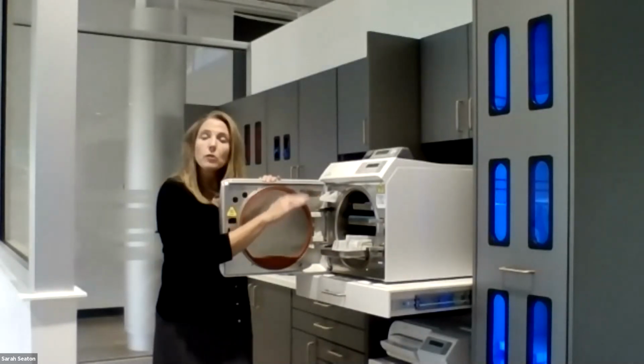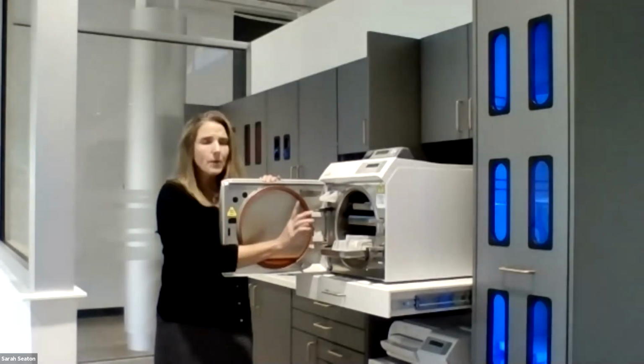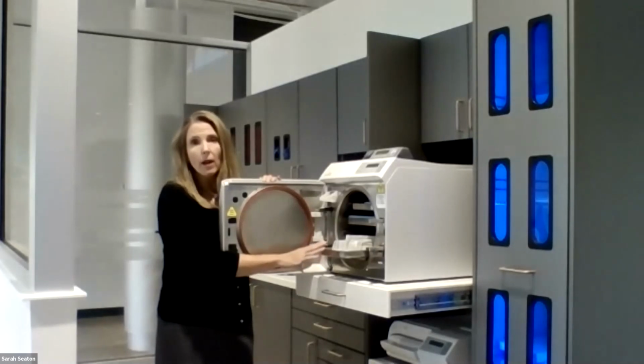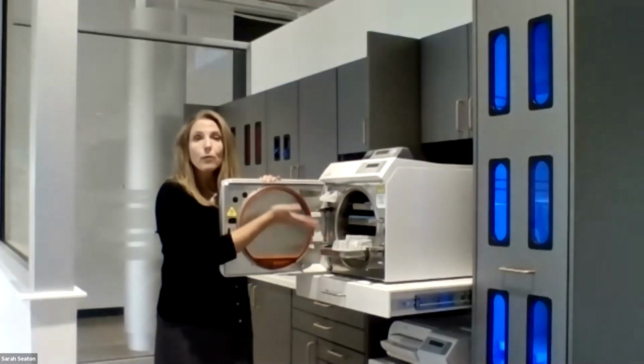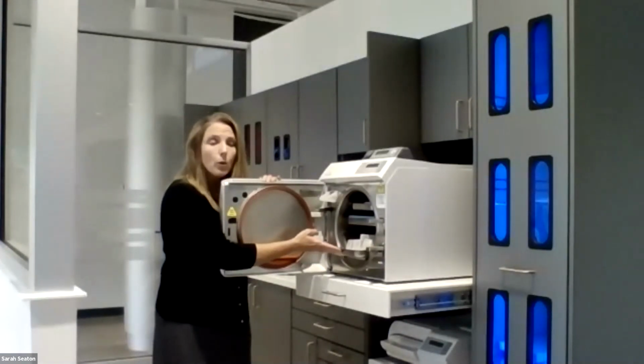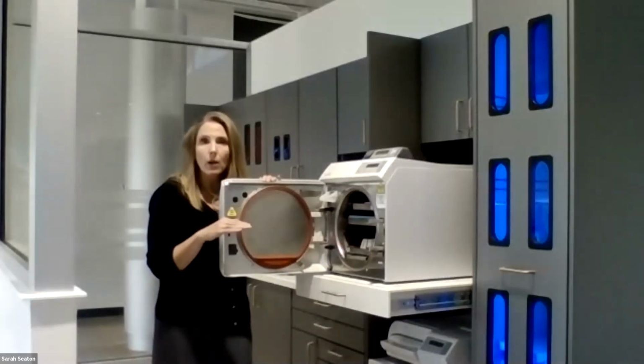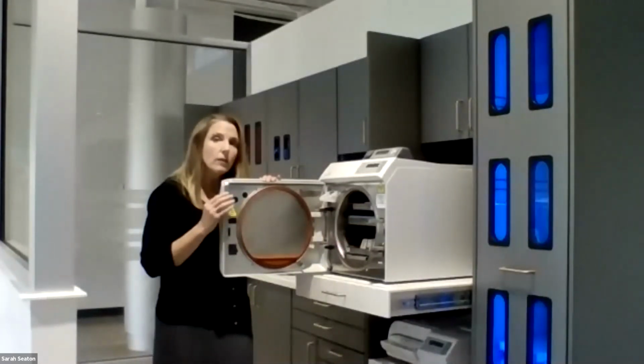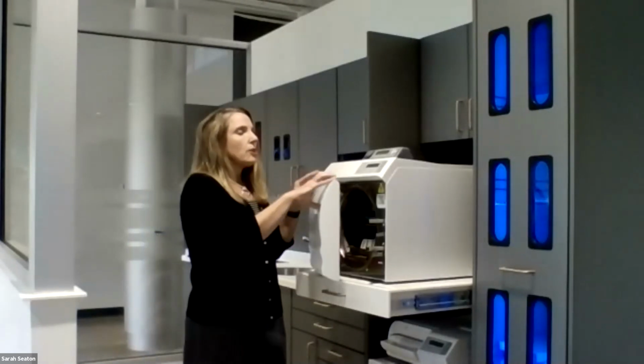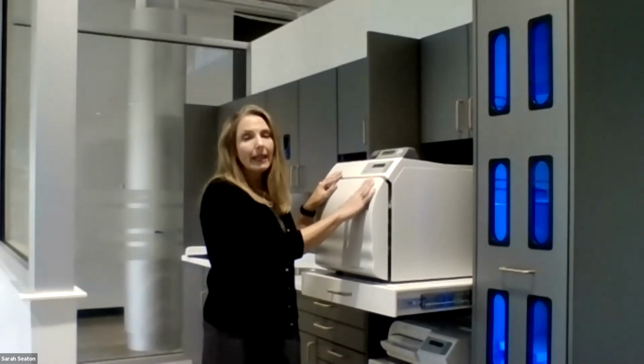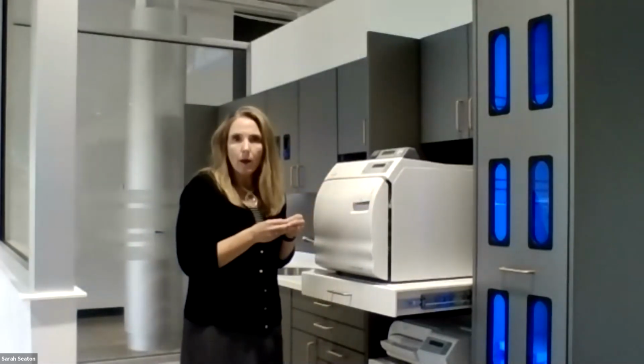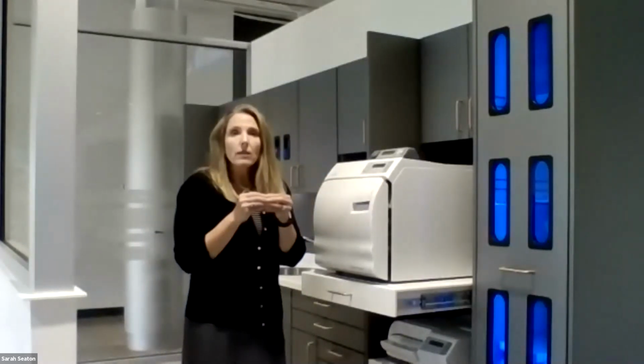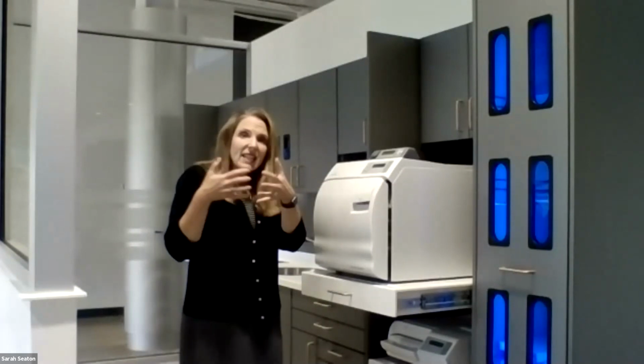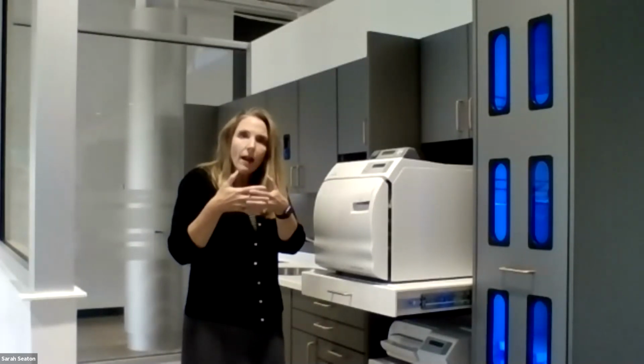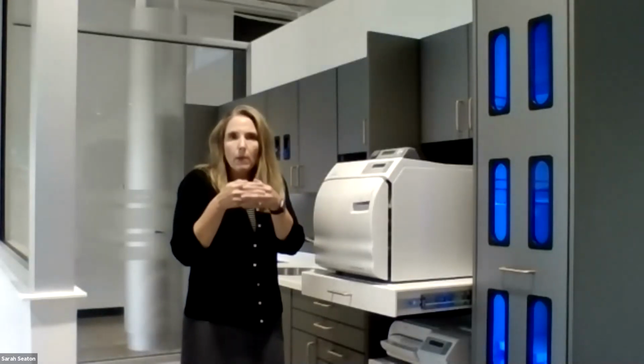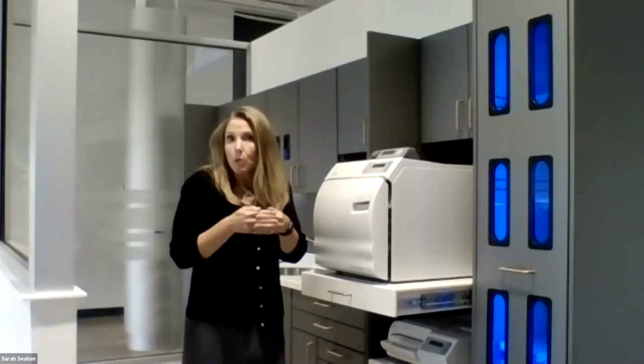If you have other pouches or if you don't have a pouch rack, we want to make sure, if you're using a pouch rack, you always want to make sure you put that pouch rack on that lowest level, again, to allow the heat to come through for drying. And then if you have other pouches that you want to load, you want to make sure that you're putting them paper side down, again, to allow for that free flow of steam and to effectively dry. The other piece with sterilization is you want to make sure that you allow the instruments to dry in the sterilizer. You don't want to be taking those wet packs out. The wrap on the packs is designed for sterility to open up to allow the heat and the steam to get to that instrument, but as that packaging dries, it closes back up and provides that sterile barrier. So you want to make sure that they're fully dry before you take them out of the sterilizer.